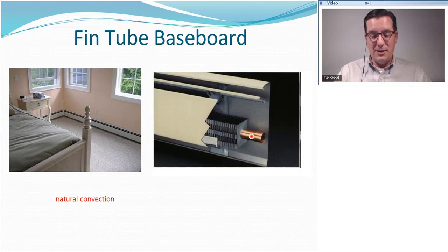There's nothing physically broken. Another way that click can happen is if a copper pipe is run right through a wooden support member and the copper is touching the wooden support, it'll do the same thing. Very difficult to solve, definitely not cheap. So when you hear that, realize we're looking at possibly replacing all these fin tube elements, and that can really sometimes bring into focus for the customer how irritating it really is, because is it thousands and thousands of dollars irritating, or maybe not. But that's generally the solution.